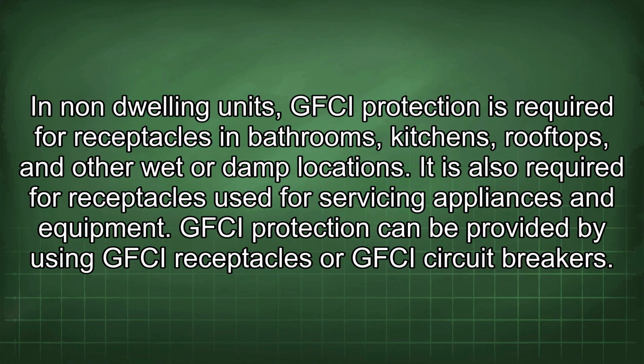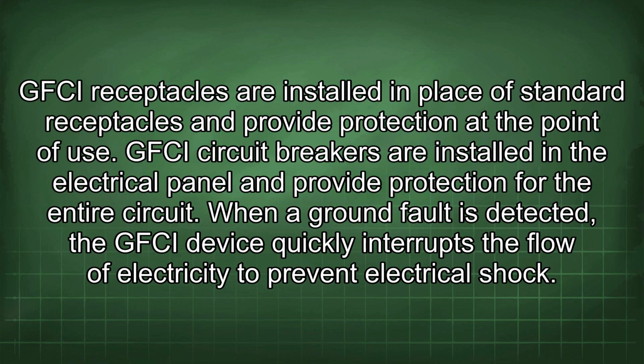In non-dwelling units, GFCI protection is required for receptacles in bathrooms, kitchens, rooftops, and other wet or damp locations. It is also required for receptacles used for servicing appliances and equipment. GFCI protection can be provided by using GFCI receptacles or GFCI circuit breakers. GFCI receptacles are installed in place of standard receptacles and provide protection at the point of use. GFCI circuit breakers are installed in the electrical panel and provide protection for the entire circuit.